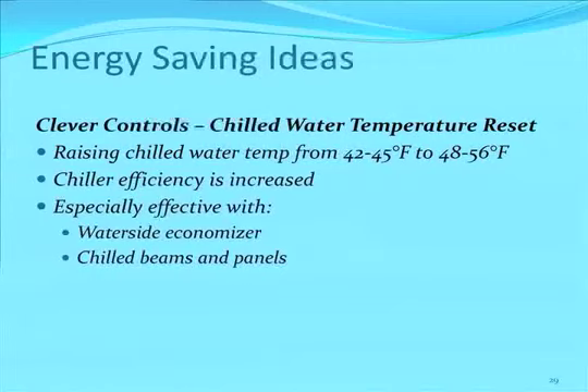And it's especially effective when you couple it with water side economizing, because then when you have a water side economizer, it can reach your chilled water temperatures, if they're higher, more often, which equates to more chiller downtime, shutdown time. Also, you can use it with chilled water beams and panels, which don't require as cold a temperature in your building.